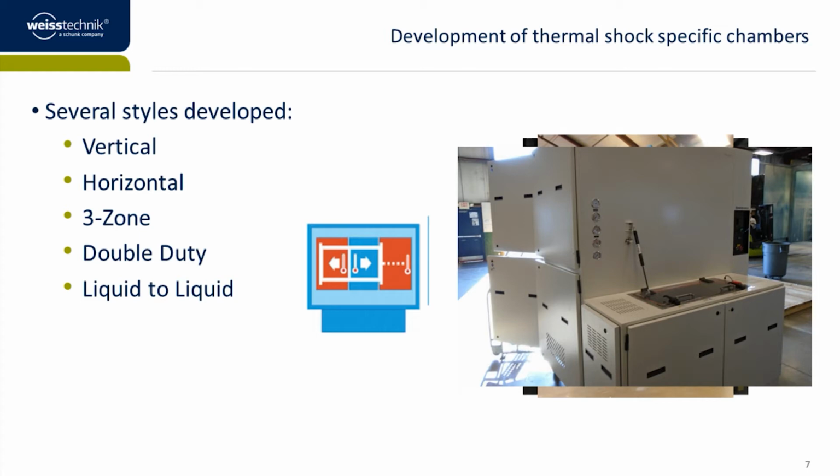periods of time. Vertical styles are really useful if you're pretty tight on footprint and you're using smaller and lighter test samples. It fits really well within the basket, and we remove the irregularity as far as transition's concerned. That basket's going to move the same time from zone to zone, from transition to transition, so it's very repeatable and reliable.